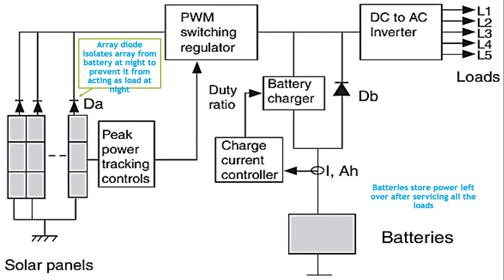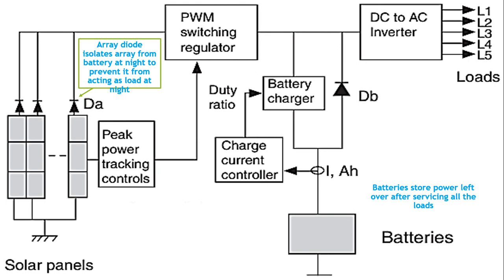This is the battery charger and this is the charge current controller. Batteries are used to store the power left over after servicing all the loads. The charge controller keeps track of the battery state of charge (SOC) by controlling system signals such as the array and battery charging currents and voltages, and activates the dump load if the battery is fully charged and residual power remains.